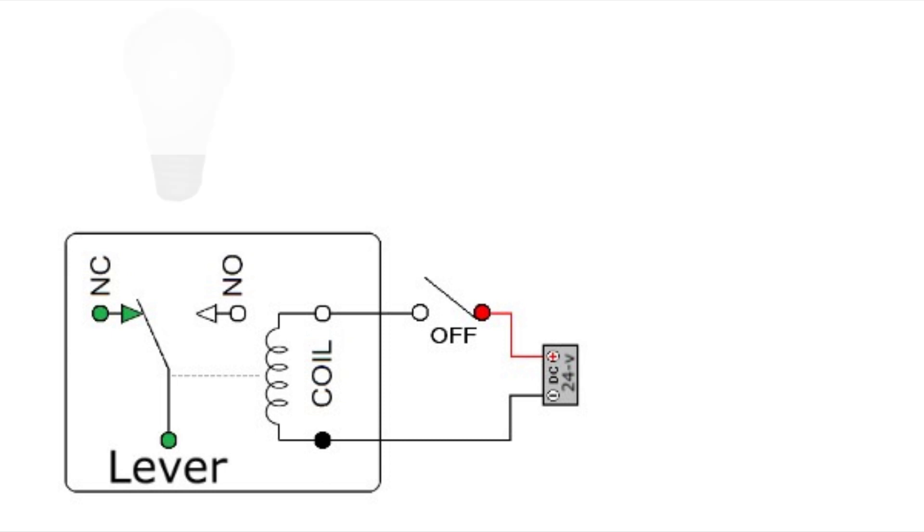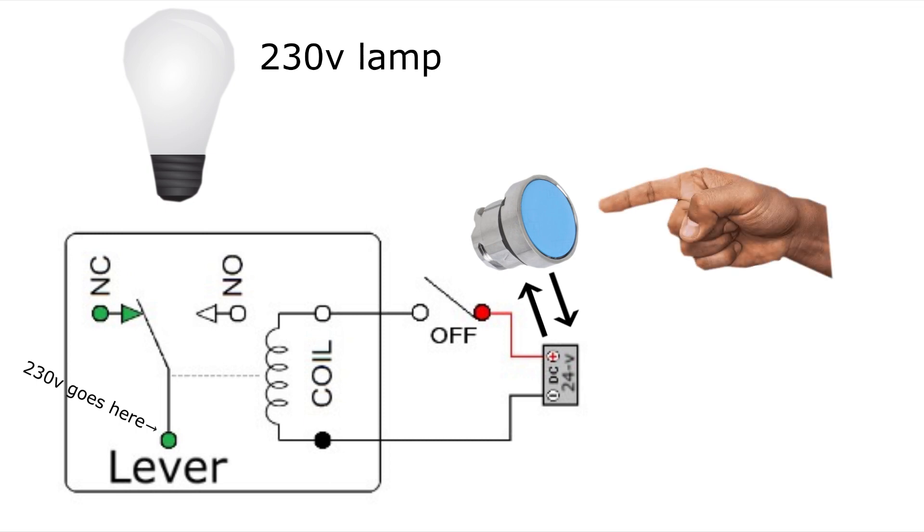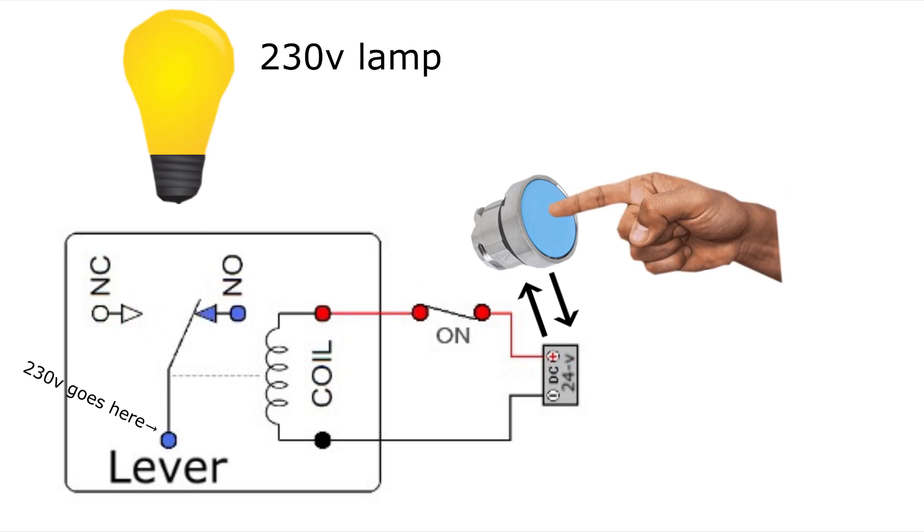To give an example, let's say we have a lamp that requires 230-voltage AC to turn on, but we don't want to use this high voltage on our button for potential dangerous electric shocks. Then we can wire up the needed voltage on the lever of the relay instead and keep just 24-voltage DC to the button. So now once we push the button, 24-voltage goes to the coil and makes the lever switch and lets the 230-voltage out to the lamp.